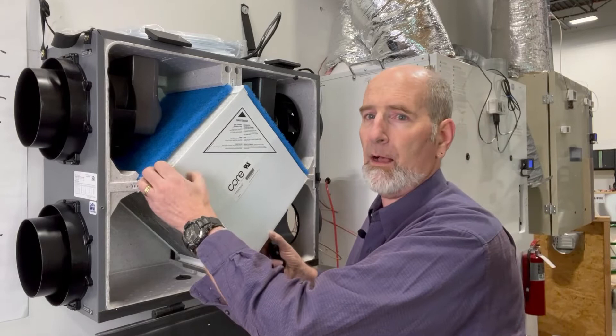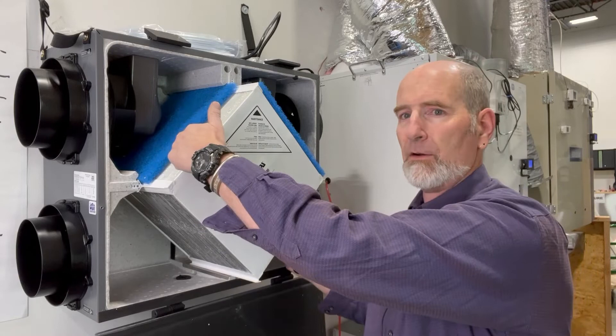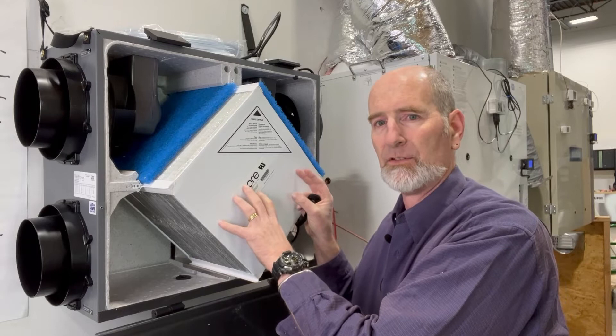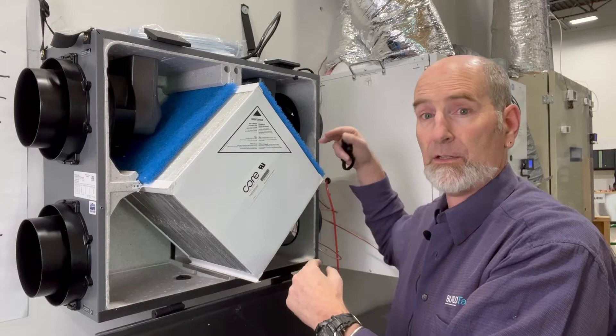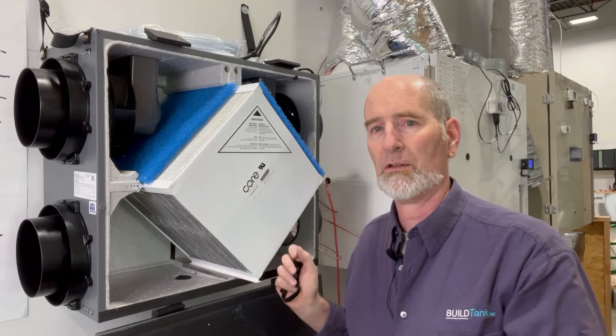The magic is these coils. This coil here — you think of it as a cardboard box that's layered in different areas. That corrugation allows air to move into the house and move from outside the house. They cross each other, but the streams of air don't physically touch each other. It's an actual type of heat exchanger to be able to transfer energy that's in the air going out of the house into the air going into the house if it's cold outside, for example. Energy is always moving from higher concentrations to lower concentrations, and it's able to do that across the coil.